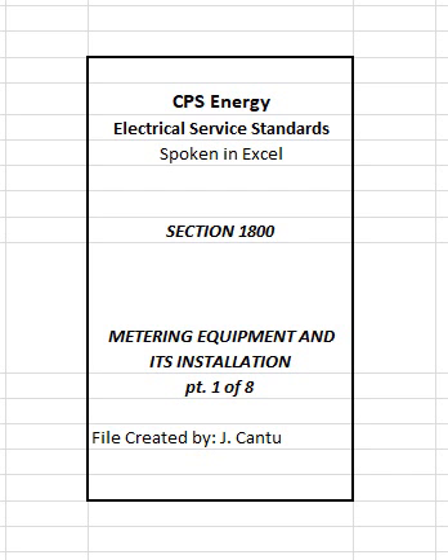A. Overhead and underground service installations. Single position, self-contained, meter sockets furnished by CPS Energy are designed to be used with either overhead or underground services. These type sockets may also be used in multiple, grouped, metering schemes where sockets are installed below auxiliary meter gutters. Sockets shall not be installed both above and below the same auxiliary meter gutter, refer to Figures 1805 and 1809. Note: the meter socket issued by CPS Energy will be based on the load to be metered and the service entrance conductor size, refer to Table 1802 for calculated load limitations.